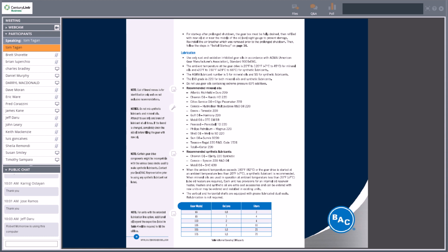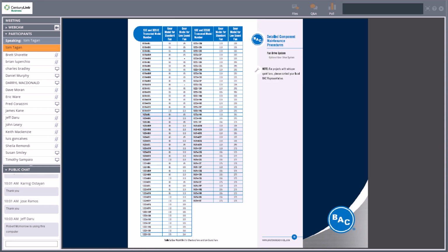Again, lubrication, with recommended oils and recommended lubricants. I think you'll find there's a number on this list that can be purchased locally at your local supplier. I think Grainger stocks a lot of these things, but whoever you normally get this type of material from, I don't think you're going to find anything on this list that's hard to find. And again, for the gear models, it tells you how many gallons, what volume you're going to need. On this page, it also lists that gear model for all of the different models of this particular unit. I think you're going to find this similar for all cooling tower manufacturers and their O&M manuals.